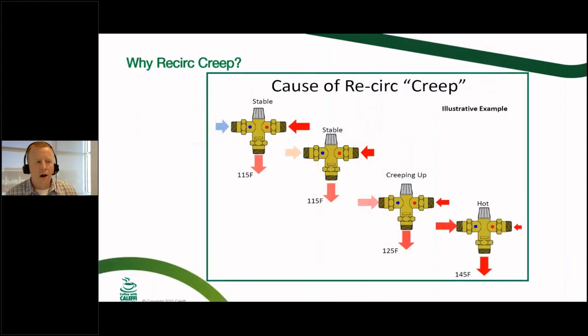So here's another quick visualization on recirc creep, just to give you it in a different form. In the upper left, you're going to have your stable operation. You're going to have high or moderate demand from your domestic hot water system or from your fixtures, and you're going to have cold water coming into the cold inlet, hot water coming into the hot inlet, and you're going to be maintaining that stable desired mixed outlet temperature, and that's perfect.